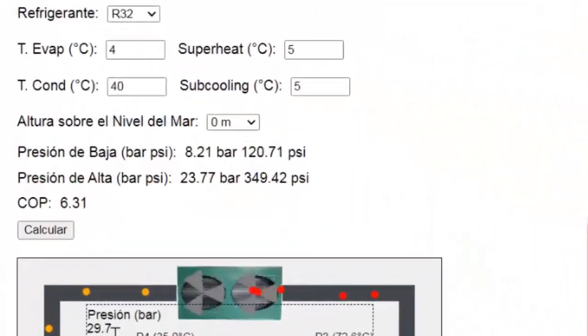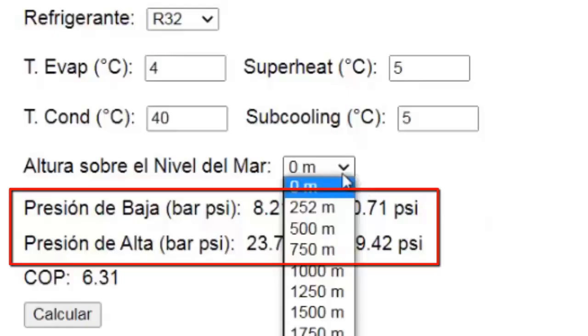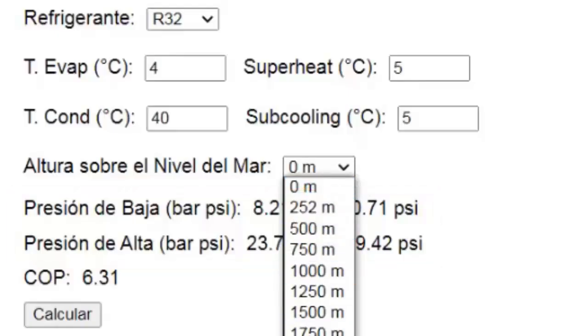The pressure indicated by the system's gauge depends on the altitude above sea level. In this field of the simulator, we can select the altitude at which the equipment is located. This allows us to obtain a more accurate gauge pressure, which is crucial for high-precision refrigeration systems.